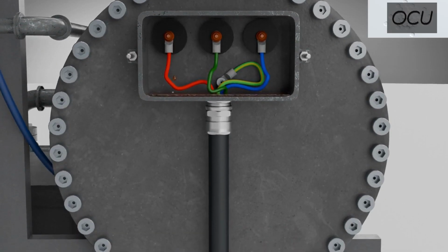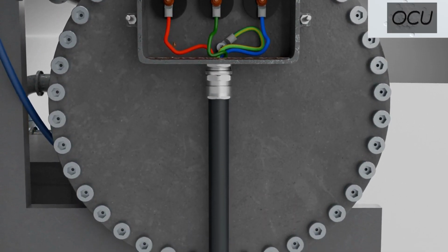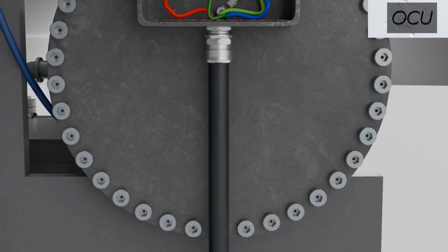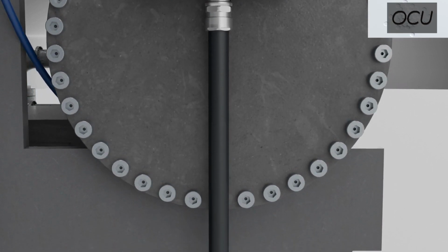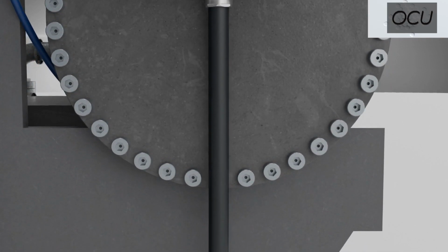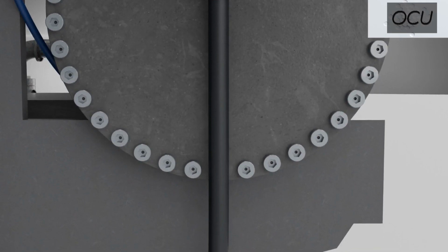It was determined that the oil traveled through the power cable, moving from the oil circulation unit all the way to the switchgear room, a distance of approximately 80 meters.